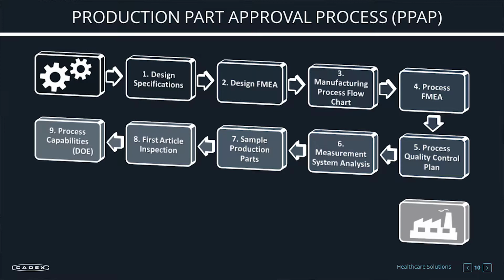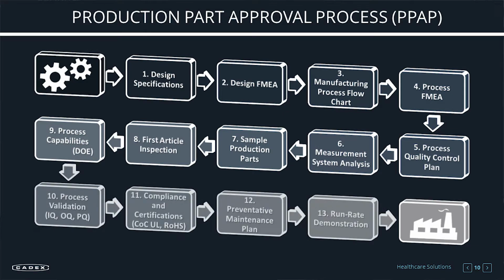The sample production parts that need to be provided, the first article inspections, the process capability analysis. So for every one of those processes, be it the ultrasonic welding process or the spot welding process, we need to assess what the variances are, what the process capabilities are, are they stable? Are we sure that if we build 1,000 or 1,000,000 pieces with the same process, all of them are really going to be good? The process validation, the IQ, OQ, PQ process there. Compliance and certifications for every component: we need to make sure that we have the certificates of conformance, the RoHS, the REACH, the Dodd-Frank conflict minerals, and whatever else comes out of there. The preventative maintenance plan for all the equipment. And this all has to be submitted to the customer and has to be available for the FDA to inspect.